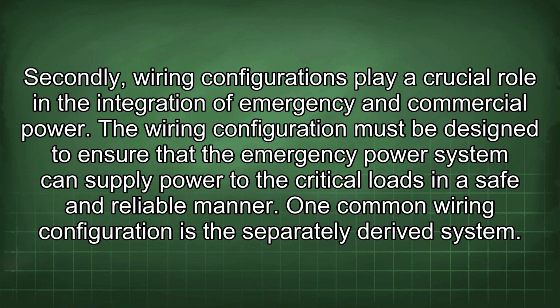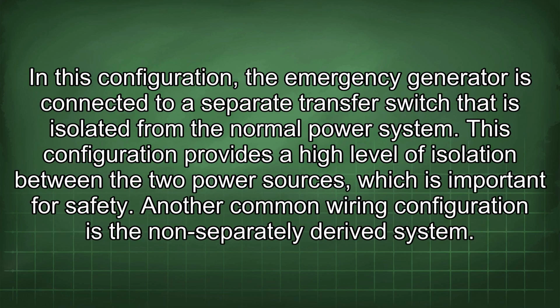Secondly, wiring configurations play a crucial role in the integration of emergency and commercial power. The wiring configuration must be designed to ensure that the emergency power system can supply power to the critical loads in a safe and reliable manner. One common wiring configuration is the separately derived system. In this configuration, the emergency generator is connected to a separate transfer switch that is isolated from the normal power system. This configuration provides a high level of isolation between the two power sources, which is important for safety.